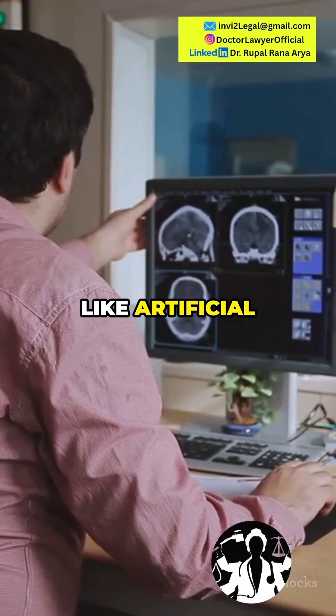CDSCO follows a risk-based model. Let's briefly go through that model. Class A is low risk or lifestyle or wellness software that only records or displays data. Class B is low to moderate, or software that supports diagnosis, but the clinician can easily override it. Class C is moderate to high, or software that drives diagnosis or treatment decisions, like artificial intelligence cancer detection or dose calculators. Class D is highest risk, or software that directly controls life-supporting devices, or can cause serious harm if it fails.